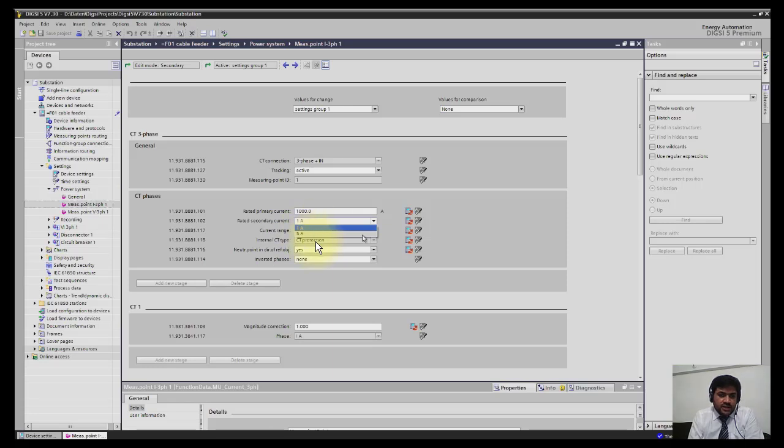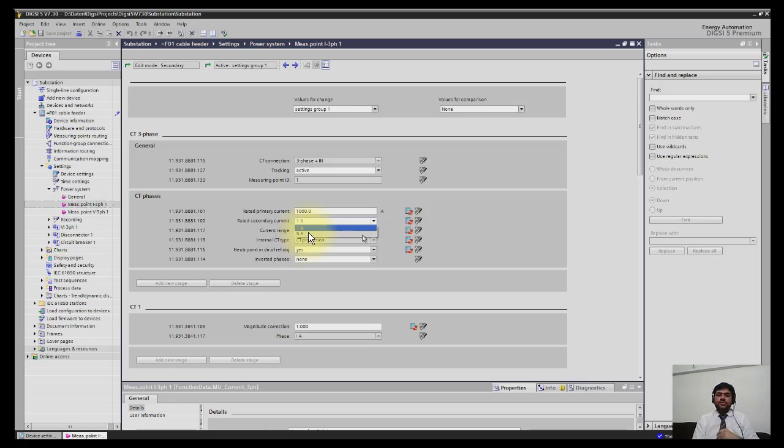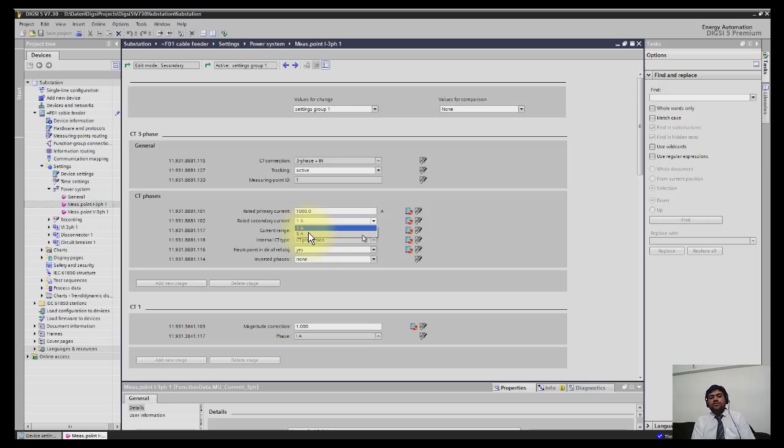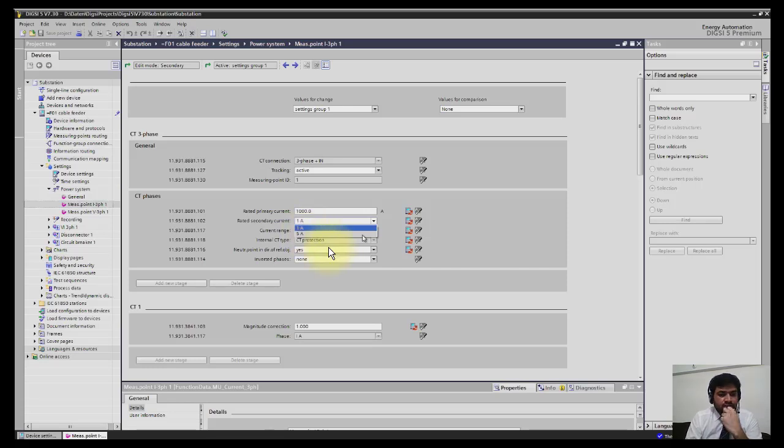DIGSI 5 is giving us great flexibility. You can select just 5 ampere or 1 ampere and you don't need to do any hardware or jumper change. In DIGSI 4 devices, if you want to change the CT secondary side from 1 to 5 or 5 to 1, you have to open the relay and change the jumper settings.